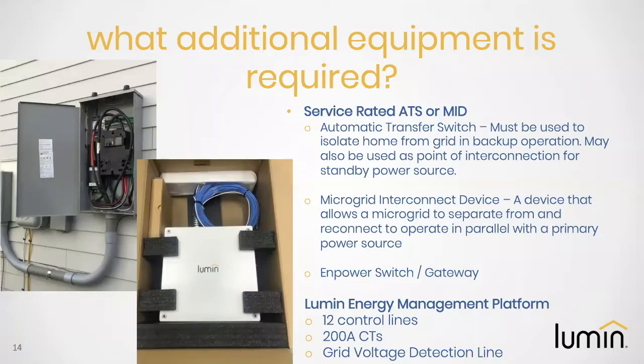A microgrid interconnect device is a newer term. It's specifically defined, I should say, by the 2020 NEC as a device that allows a microgrid to separate from and reconnect to operate in parallel with a primary power source. Examples of these MIDs might include the Tesla Gateway or the soon-to-be released Enphase Ensemble, their Enpower switch. So it's a newer term, but in many ways serves a very similar purpose as a traditional ATS.